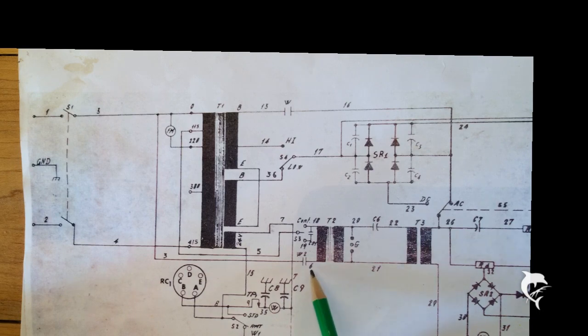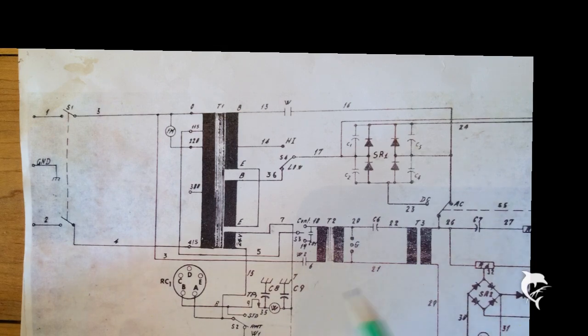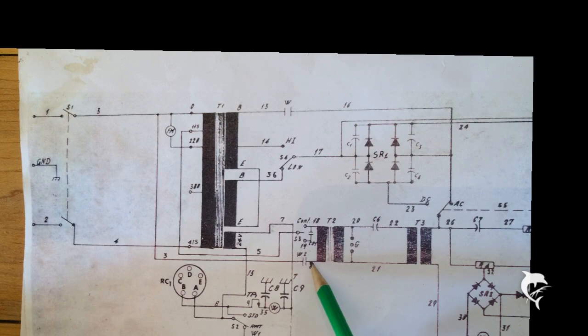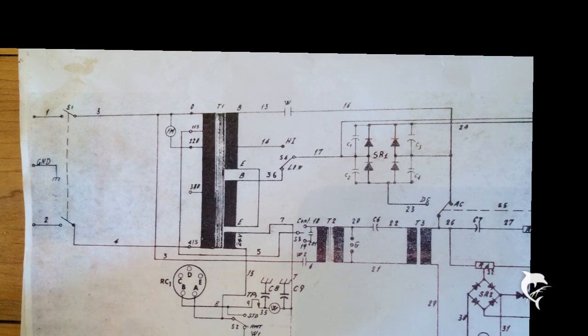And they've given you a hint with this symbol, which is a stranger to me, although I think it signifies a pair of contacts. So it signifies pair of contacts or contactor number two. And a number next to the wire, which signifies the number on the wire. All the wires in this welder are black. And they all have numbers on them in white, which are very difficult, sometimes impossible to read as they get older. But I've managed. So this wire here should be number six, and this wire that continues here should be number three.